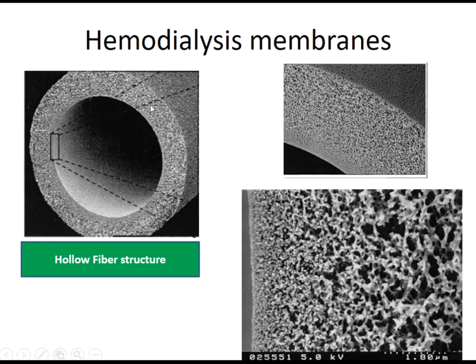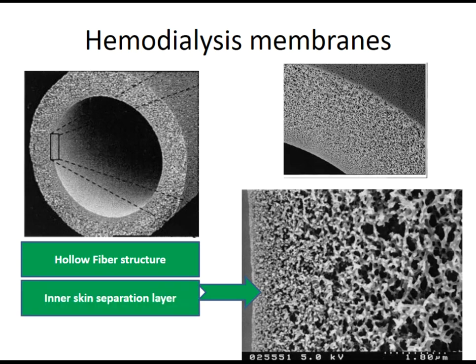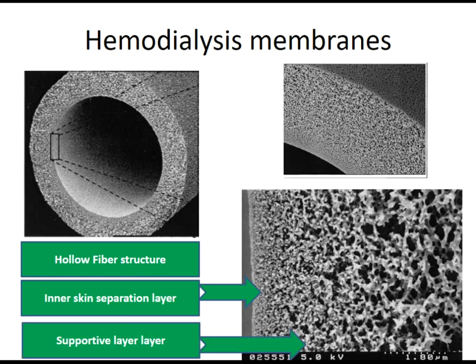Each fiber has a hollow structure for the blood pathway and a wall. The internal diameter and wall thickness are visible in the cross-section. In the wall, there is a separation layer — the inner skin separation layer is the most important layer for sieving, determining which solutes or molecules can pass — and a supportive layer.